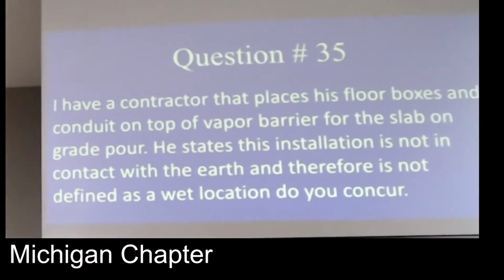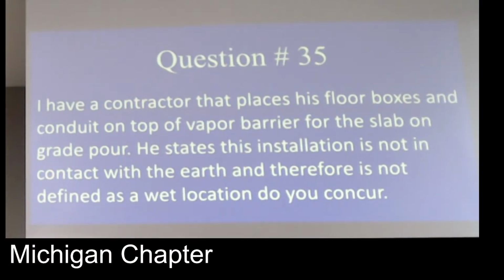a contractor that places floor boxes and conduit on top of the vapor barrier for the slab, for slab on grade. He states his installation is not in contact with the earth and therefore not defined as a wet location. Do you concur? This comes under the oh no you don't section of the code.